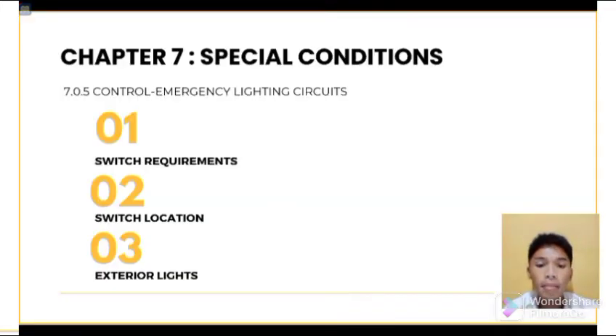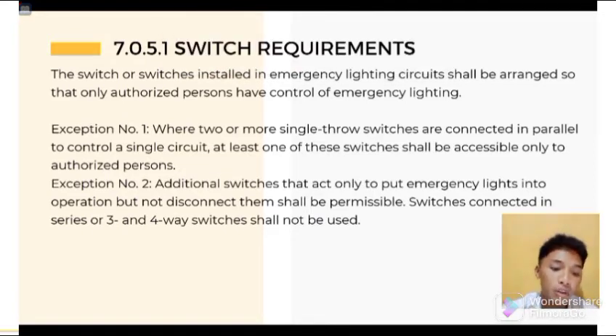Okay, so control of emergency lighting circuits. Switch requirements. The switch or switches installed in emergency lighting circuits shall be arranged so that only authorized persons have control of emergency lighting. So there are two exceptions in here. Exception number 1, where two or more single throw switches are connected in parallel to control a single circuit, at least one of these switches shall be accessible only to authorized persons. Exception number 2, additional switches that act only to put emergency lights into operation but not disconnect them shall be permissible.